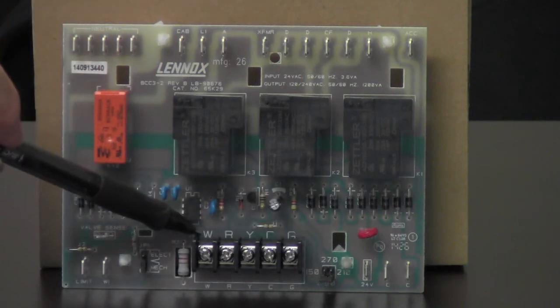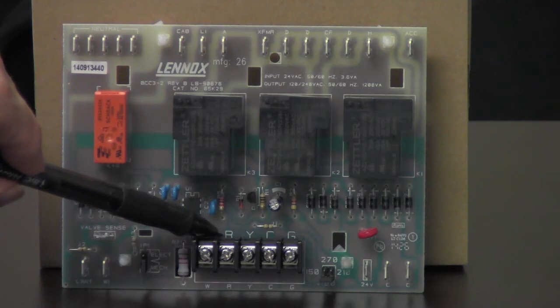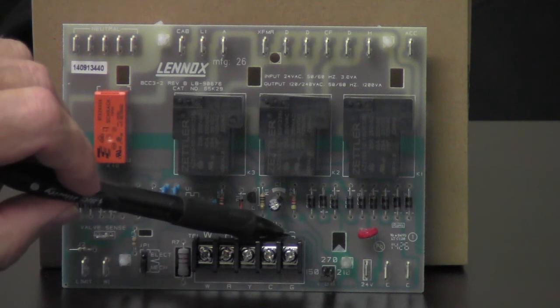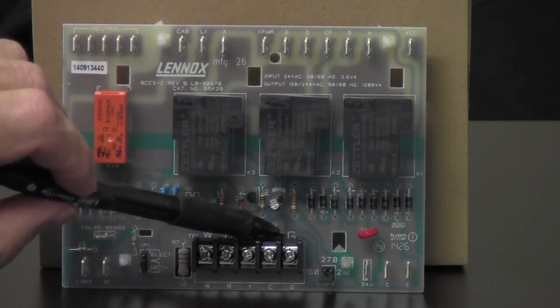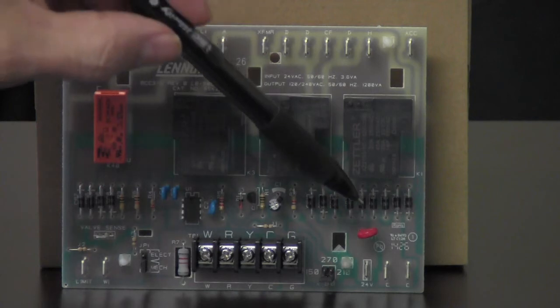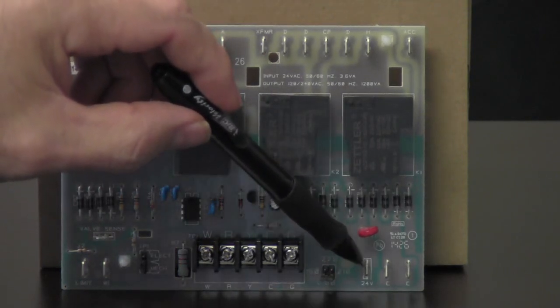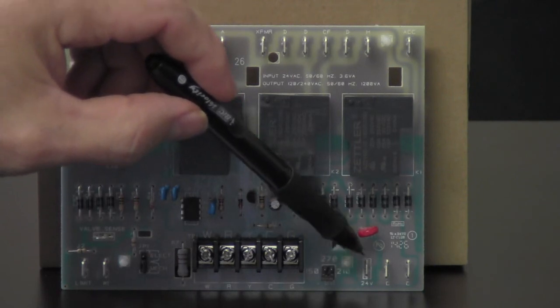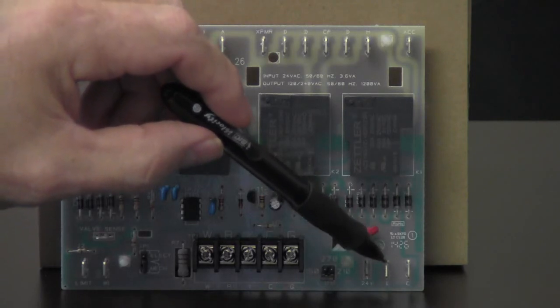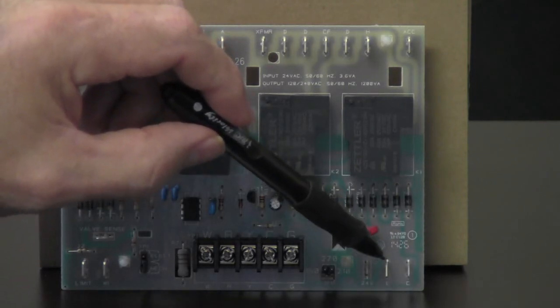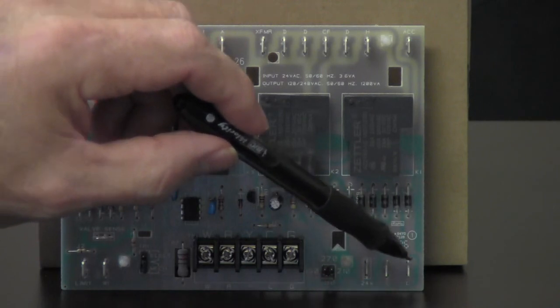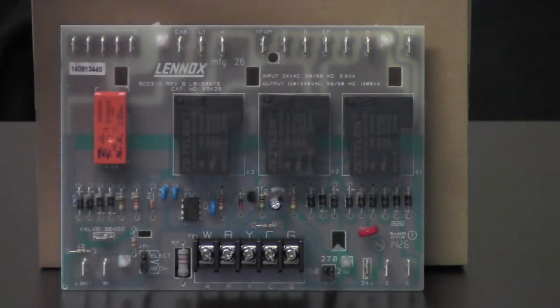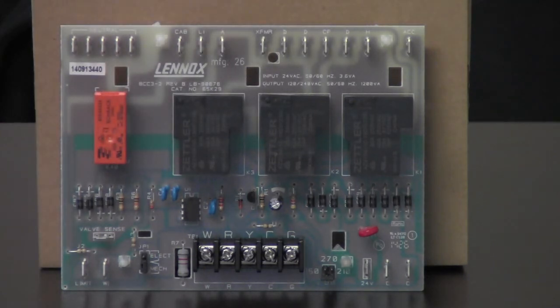W, that's for our heat demand. R is our 24 volt going in. Y is for our cooling. We got C, that's our common. And G, which is for our fan. Right over here on the bottom is our 24 volt coming from the transformer, usually secondary side of the transformer, usually a blue wire. And we got our C and our C, that's going to be our common coming from the transformer. Like I say, this board is pretty easy, pretty simple. There's not much to it.